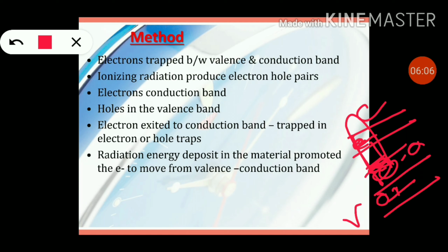If the center of the hole is a luminescent center, then the emission of light will occur. So photons are detected by the photomultiplier tube. The signal from the tube is then used to calculate the dose that the material has absorbed.